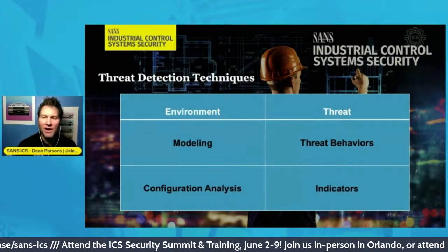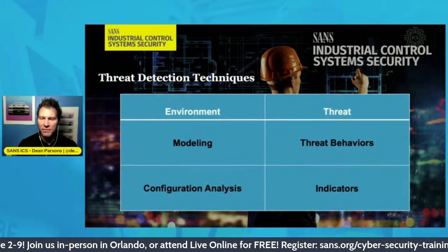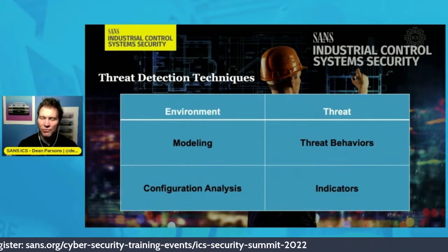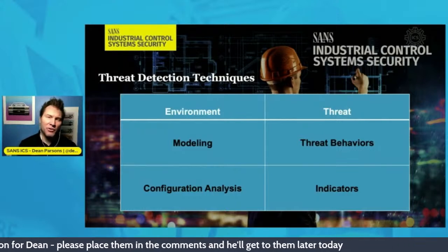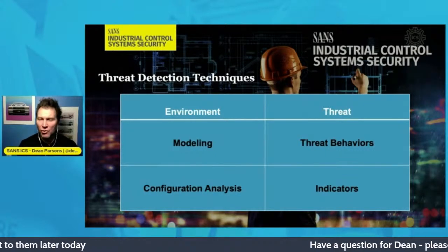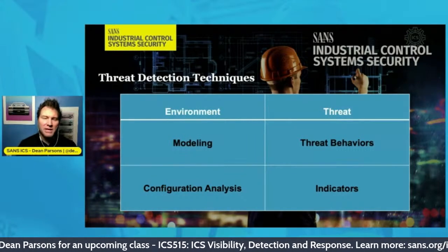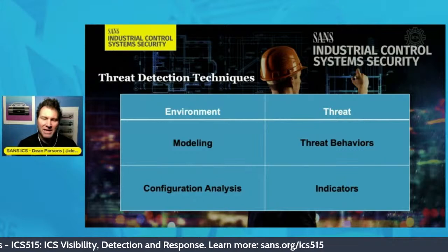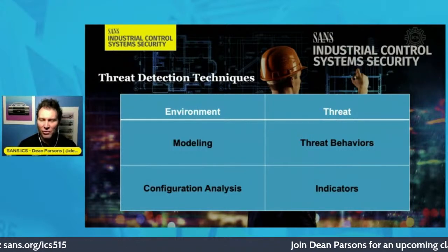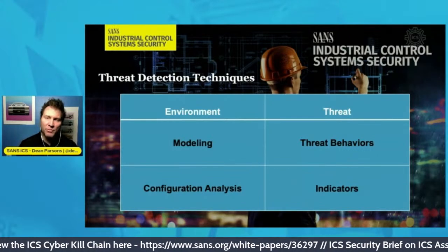Under the environment category, if we focus on configuration analysis, we're going to be spotting those changes that the adversary made in the environment. Any change in the environment can generate a ton of false positives with this methodology, but we can reduce that. The most important thing is which changes you're going to track. Specific to the ICS environment and using threat intelligence — are you detecting changes in the programmable logic controller project file? Anytime a PLC at the heart of the ICS is changed, that's cause for concern if it's not an authorized, legitimate internal change.